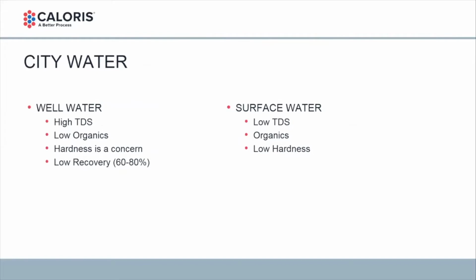City water, pretty good water. The only issue is that if you're getting it from well water, you're going to have high TDS. You need to plan for that in your RO. It's going to have probably low or no organics, which is a good thing. Hardness is your biggest concern, and because of the hardness in the water, you're only going to get a recovery of 60 to 80%, so it's a low recovery. And if the source is surface water, it's probably going to have low TDS, but you're going to have organics, which you need to plan for. And then you're probably going to have low hardness.